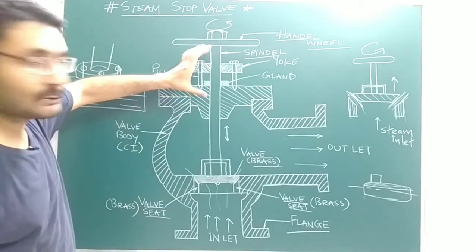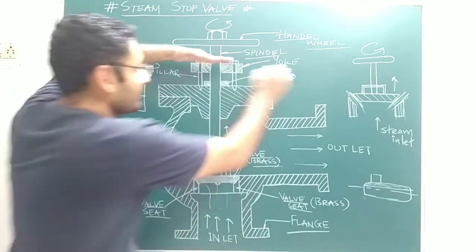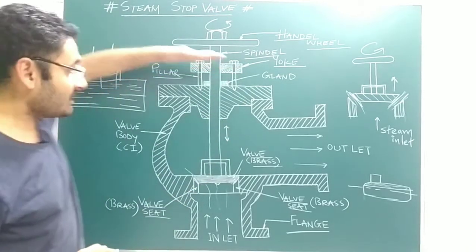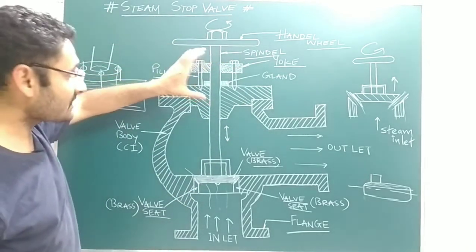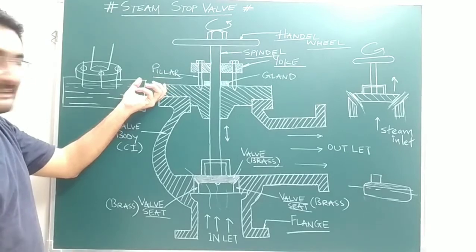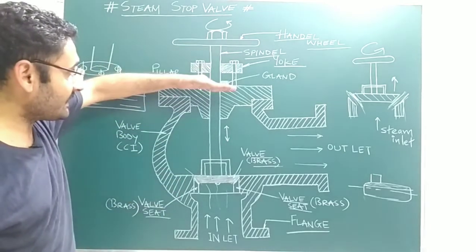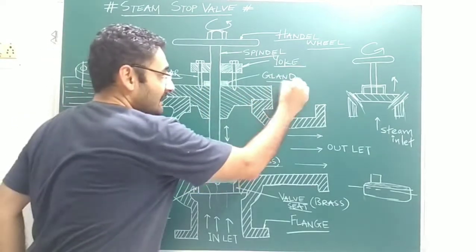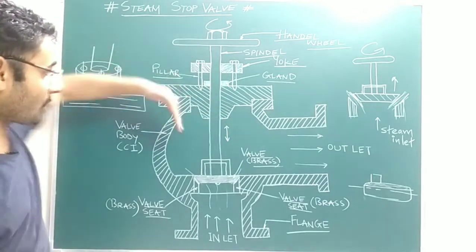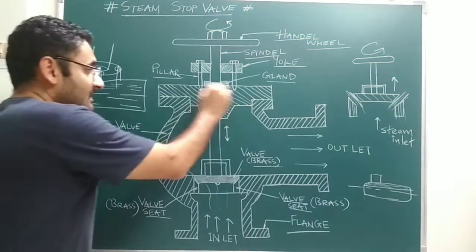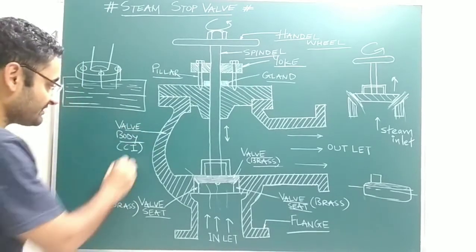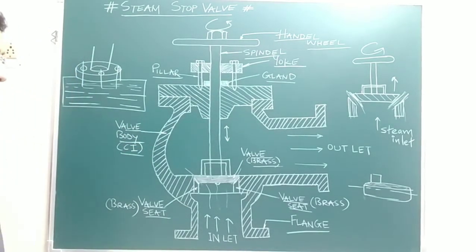Because the spindle is very long, a yoke is used to support some of its length so that misalignment is not present. The pillars — which are a type of bolt or stud — support the yoke. Below the yoke, the dark portion is known as the gland. The gland is used to avoid steam leakage from the steam stop valve. The entire outer structure is the valve body, which is made with cast iron material.